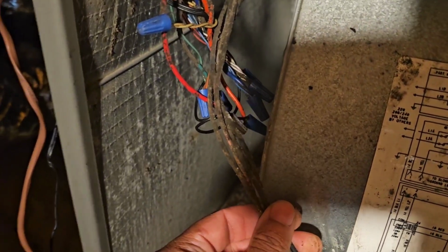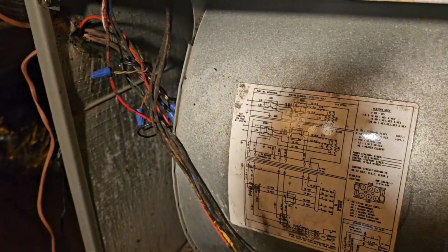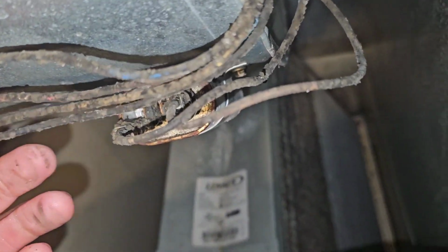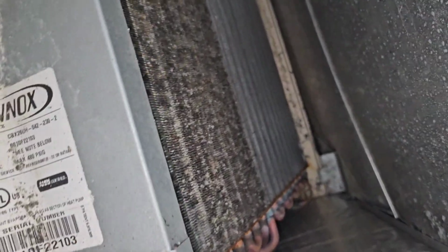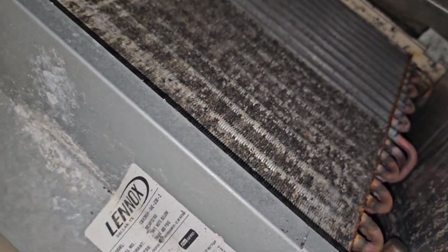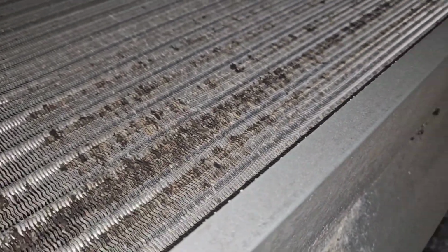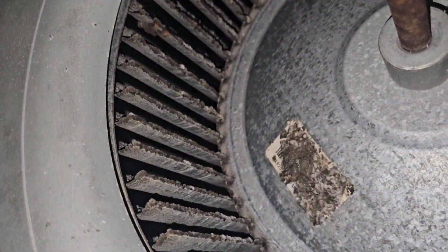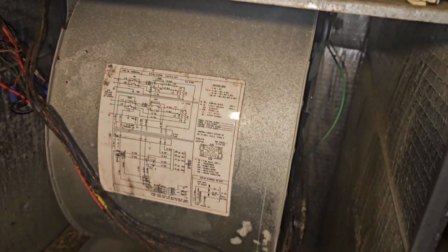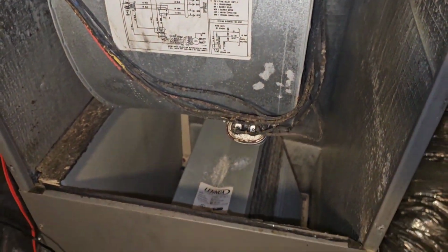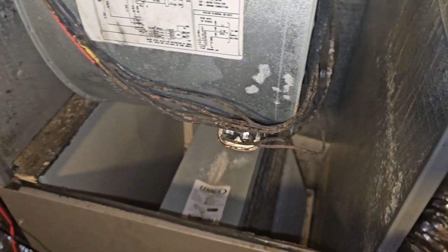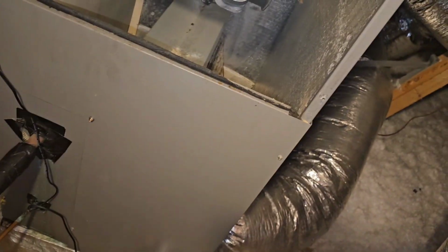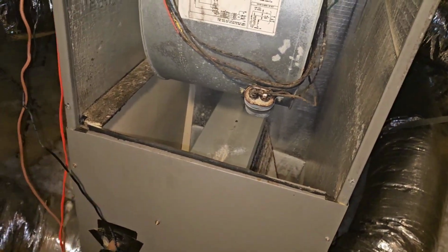That could have caused a rub out issue right there. But I mean, I've never seen on the positive side, no, the supply end of the evaporator coil, because that's technically what this is - I've never seen growth this bad. I mean, and it's all on there, on the blower motor. I mean, we're gonna have to quote them out for a good cleaning, because if the evaporator is that bad on this side, I don't even want to know what it is on the opposing side. I can't get the tripod in there to see that.